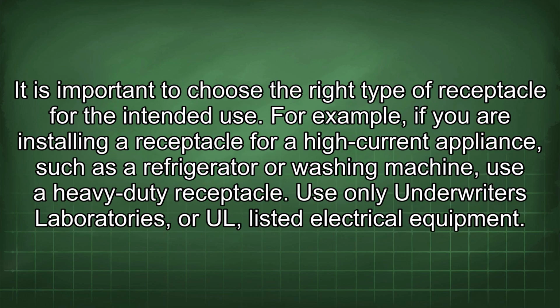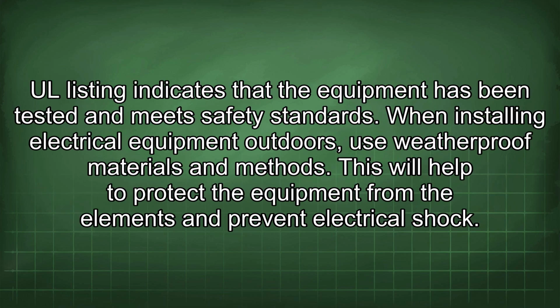It is important to choose the right type of receptacle for the intended use. For example, if you are installing a receptacle for a high current appliance, such as a refrigerator or washing machine, use a heavy-duty receptacle. Use only Underwriters Laboratories, or UL, listed electrical equipment. UL listing indicates that the equipment has been tested and meets safety standards. When installing electrical equipment outdoors, use weatherproof materials and methods. This will help to protect the equipment from the elements and prevent electrical shock.